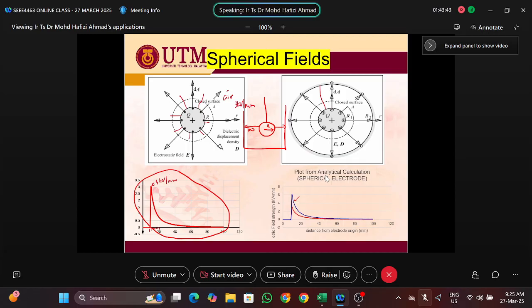For this spherical electrode hanging in free space, at a certain voltage level, the higher electric field exists at the surface of the electrode. I can't remember exactly what voltage I used here, but the electric field can reach up to 3 kV per millimeter. If the electric field exceeds 3 kV per millimeter and the ball electrode is surrounded by air, it can cause discharge—some corona discharge may happen on the surface of the electrode.